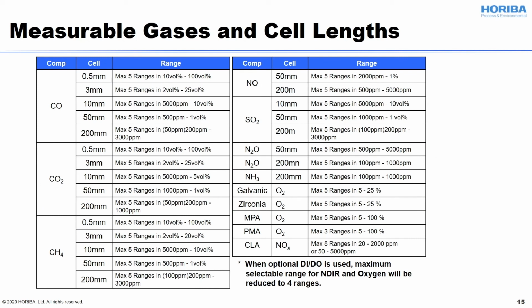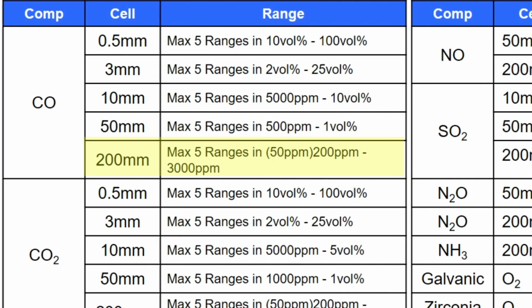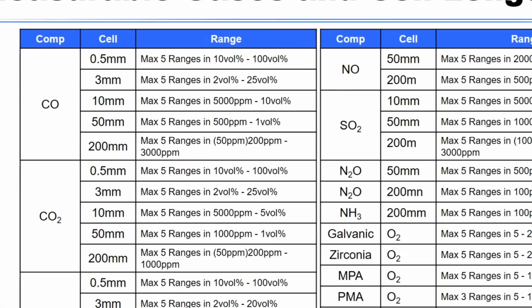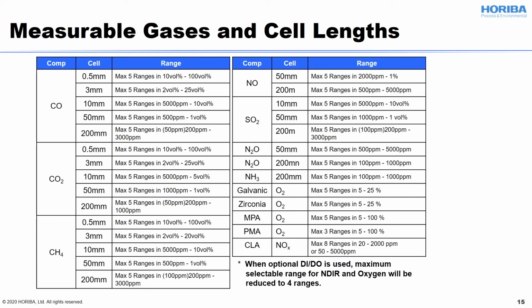Here is a table for the basic measurement of components: CO, CO2, CH4, NO, SO2, N2O, ammonia, O2, NOx. As you can see, those parameters can cover from 100% to ppm level by providing different types of cell. Basically, a longer cell can measure lower concentrations, and a short cell is for higher concentrations. Also, I wanted to say each cell can have up to 5 ranges.